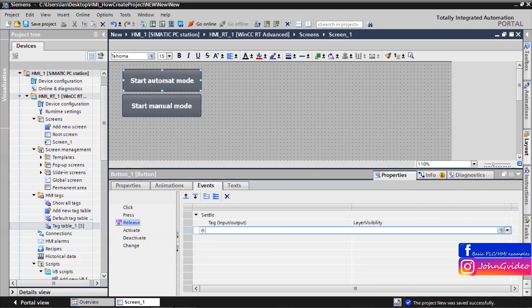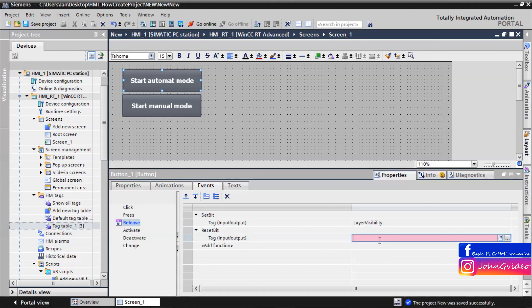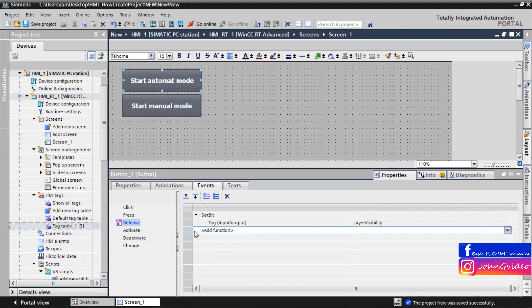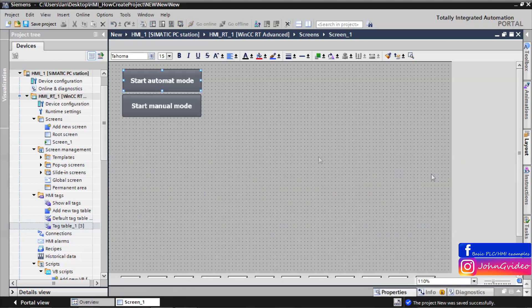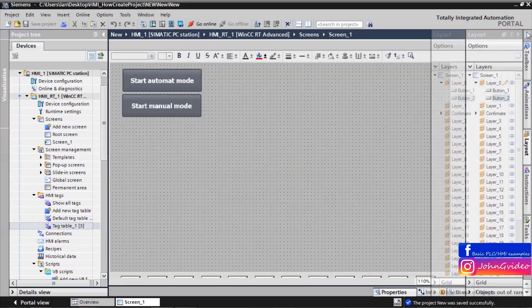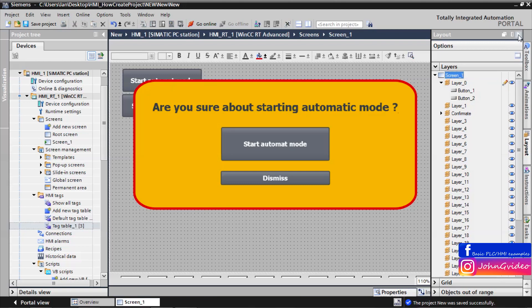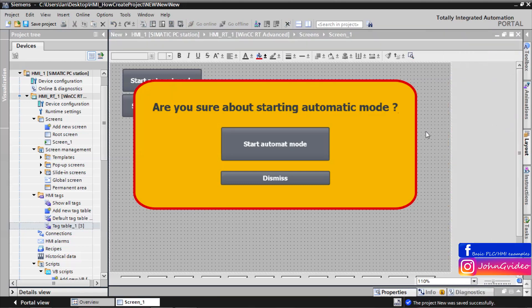In the 'Start Automatic Mode' button, we do not reset the tag here, because this we use in the confirmation window. Now we go back to the confirmation window — where if the 'layer_visibility' process tag is set to true, then we want to make this confirmation window visible. When the 'layer_visibility' tag is 0 (false), then we hide this confirmation window.